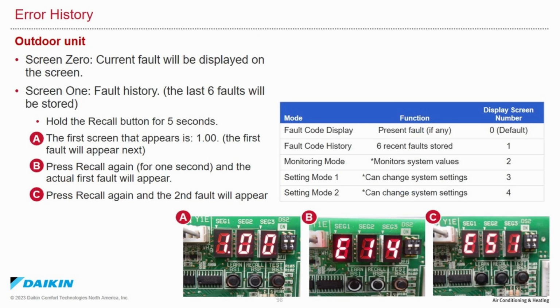Outdoor unit error history. Screen 0, the current fault will be displayed on the screen. Screen 1, fault history, which will store the last 6 faults. Hold the recall button for 5 seconds. The first screen that is displayed is 1.00. The next thing that appears will be the first fault. Press recall again for 1 second and the first fault will appear. Press recall again and the second stored fault will appear, and so on.